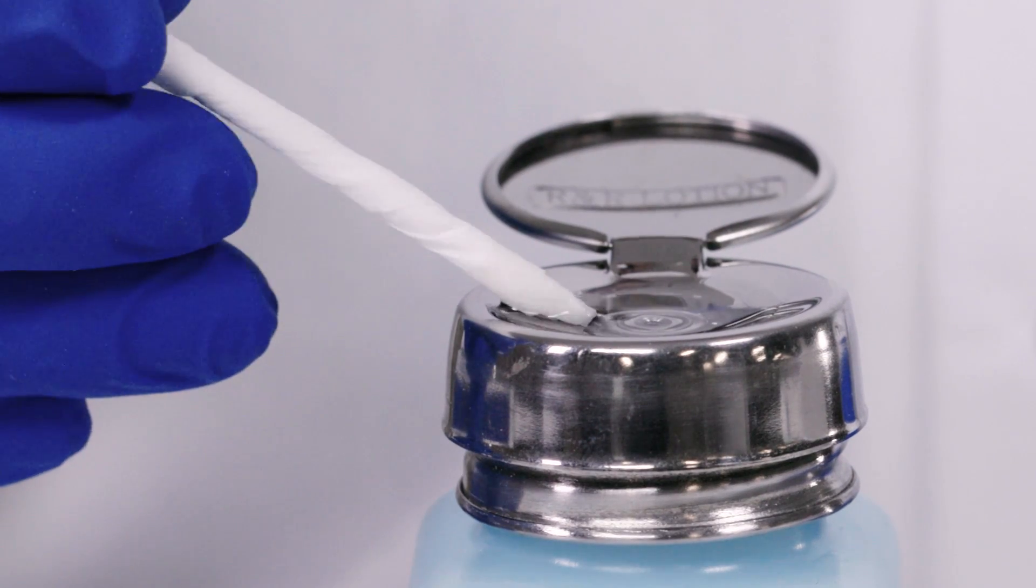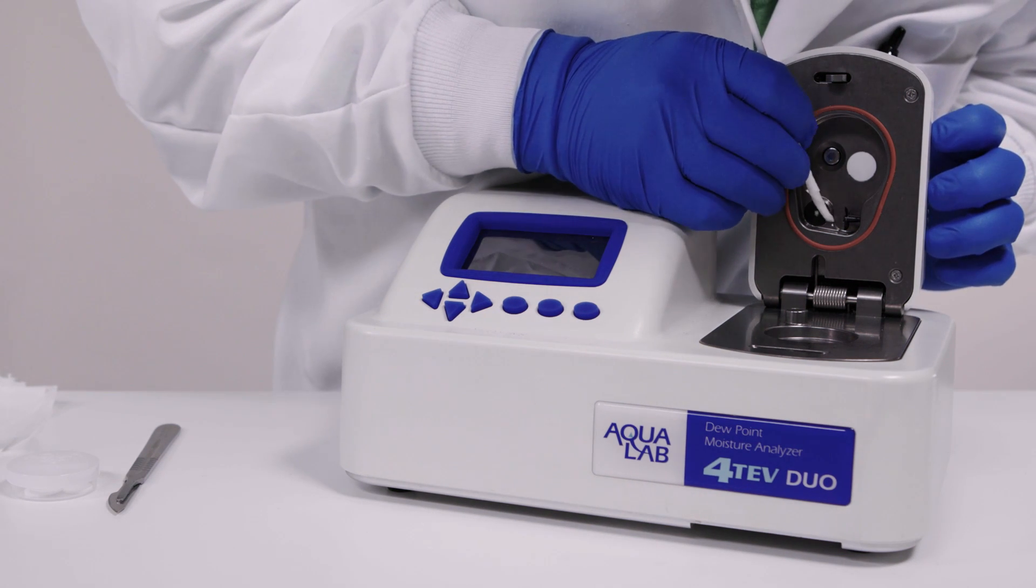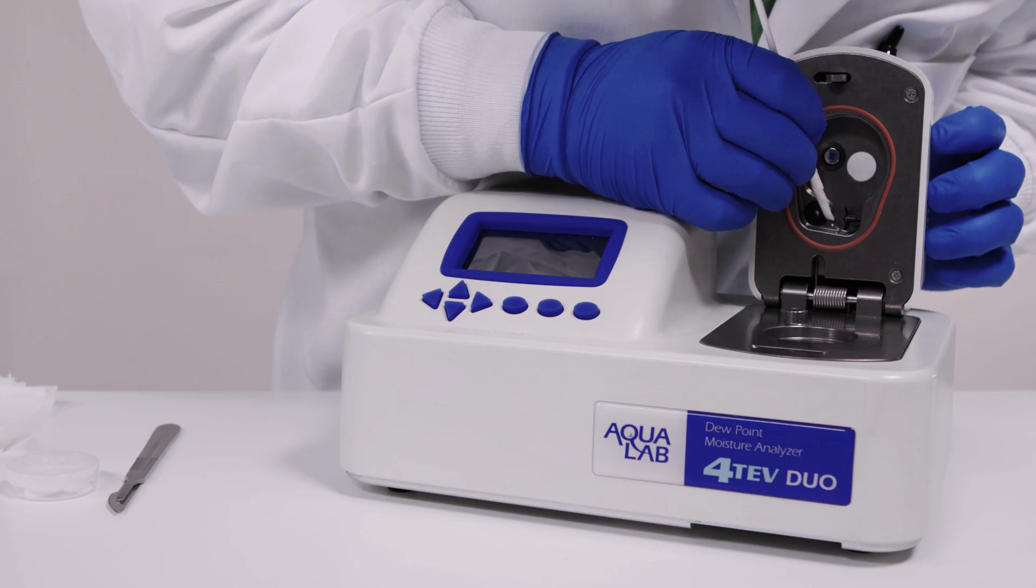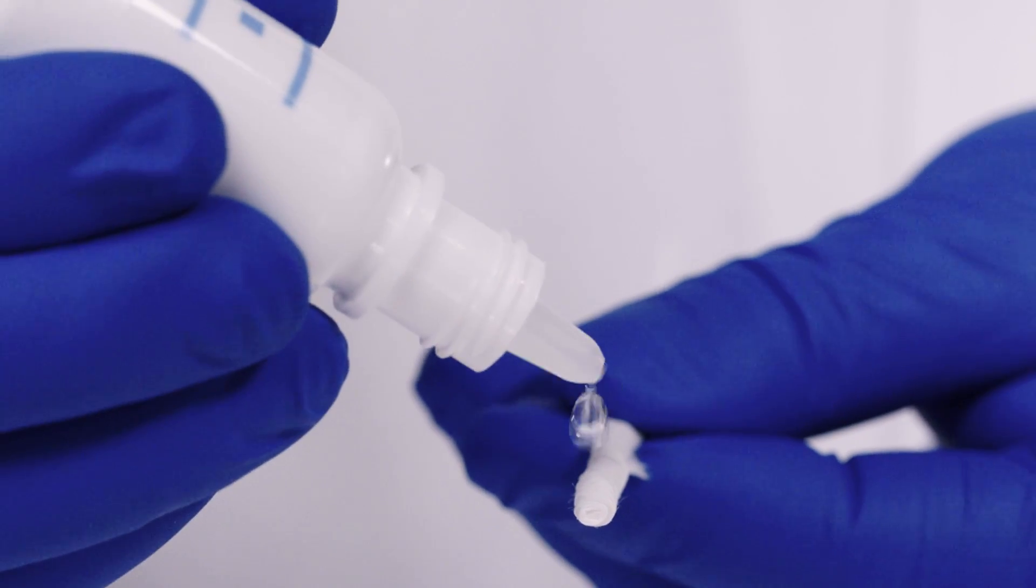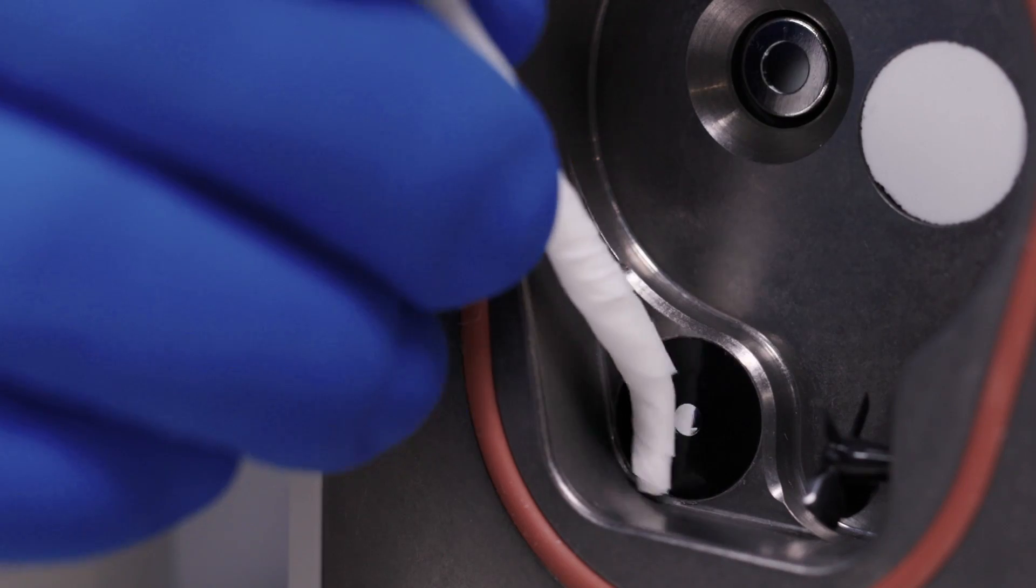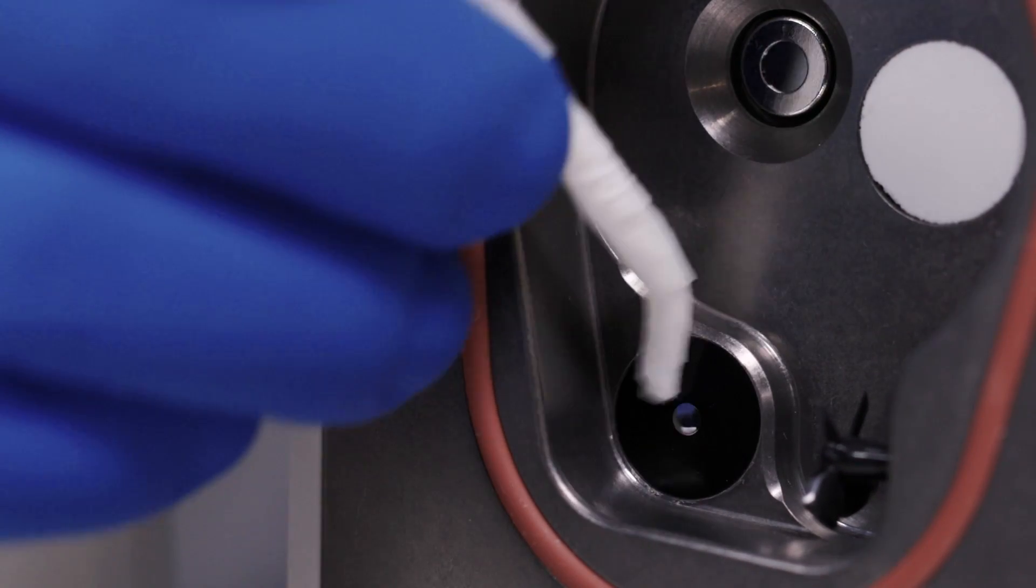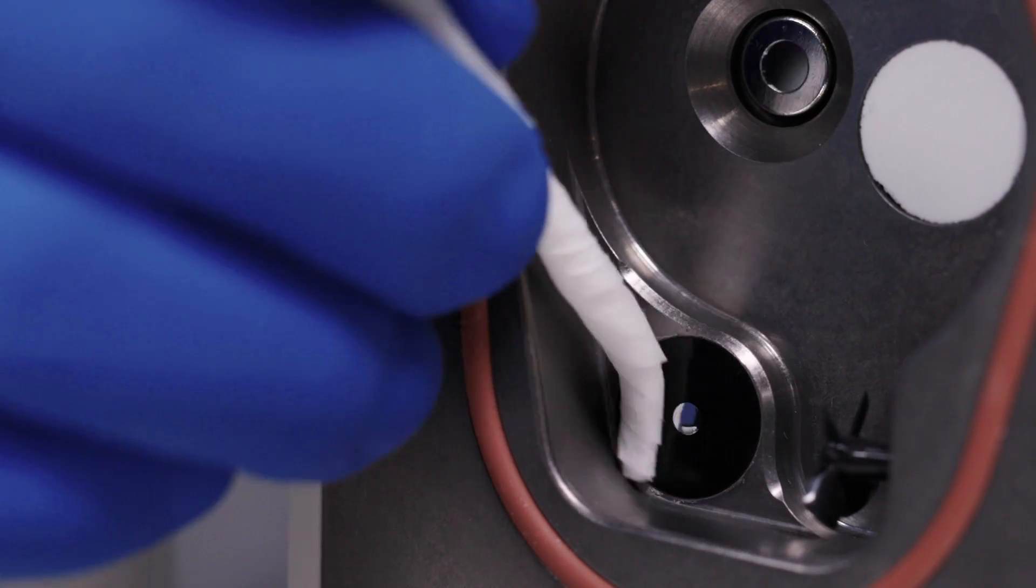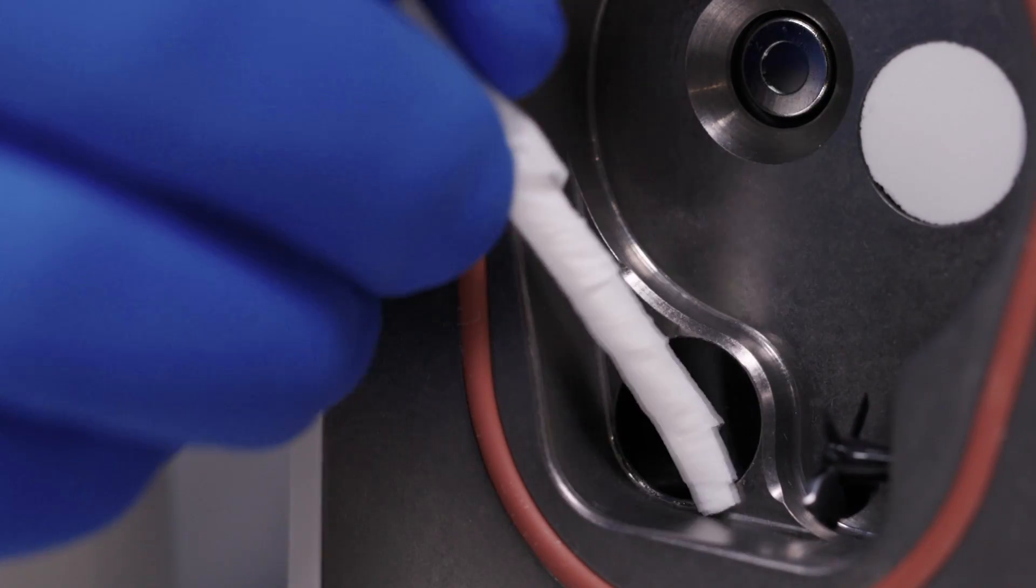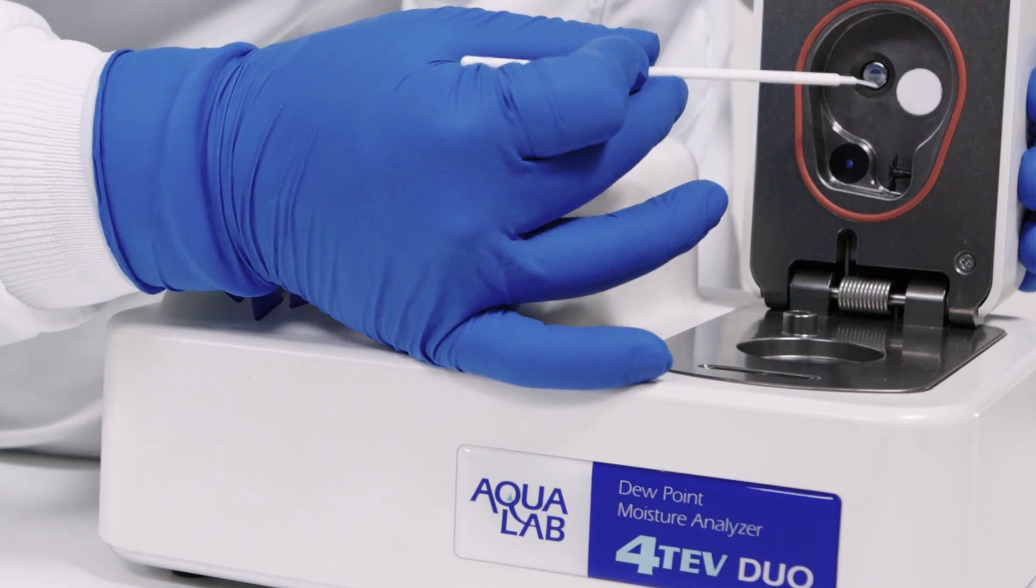This video shows the cleaning of the mirror. The thermopile and the optical sensor should be cleaned in the same way. Clean each sensor separately by wiping across the sensor. Again first with a clean kimwipe and isopropyl alcohol or cleaning solution, then with a fresh kimwipe and distilled water, and finally with a clean dry kimwipe. Repeat the same process for the thermopile and the optical sensor.